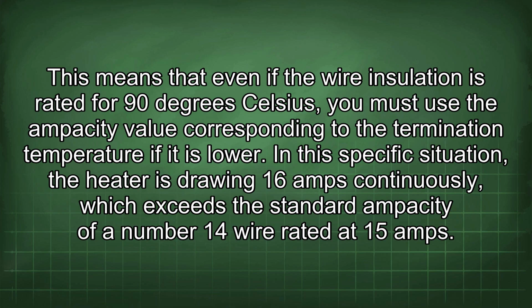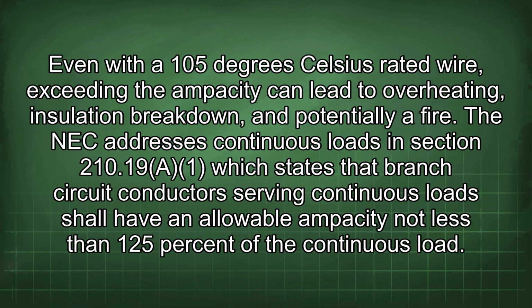In this specific situation, the heater is drawing 16 amps continuously, which exceeds the standard ampacity of a number 14 wire rated at 15 amps. Even with a 105 degrees Celsius rated wire, exceeding the ampacity can lead to overheating, insulation breakdown, and potentially a fire. The NEC addresses continuous loads in section 210.19(A)(1), which states that branch circuit conductors serving continuous loads shall have an allowable ampacity not less than 125% of the continuous load.